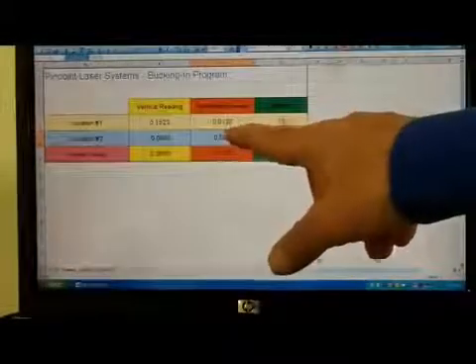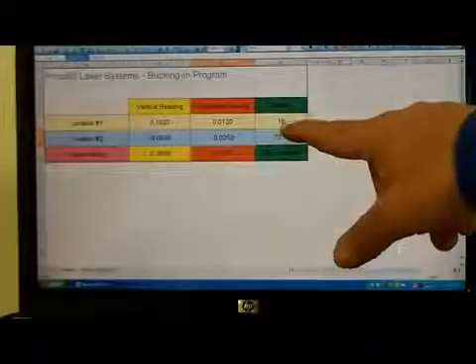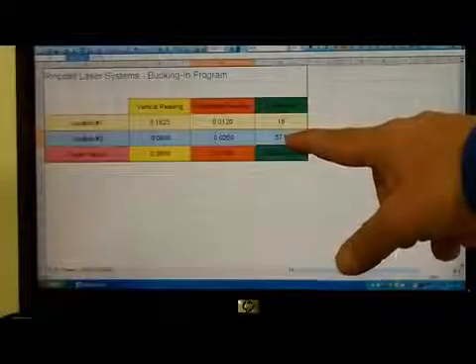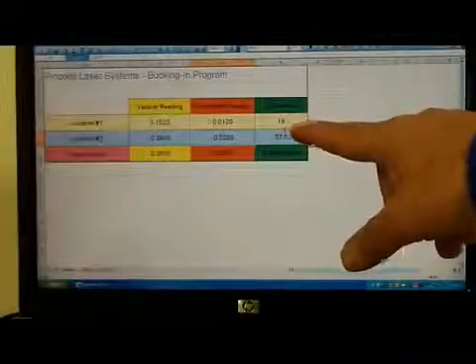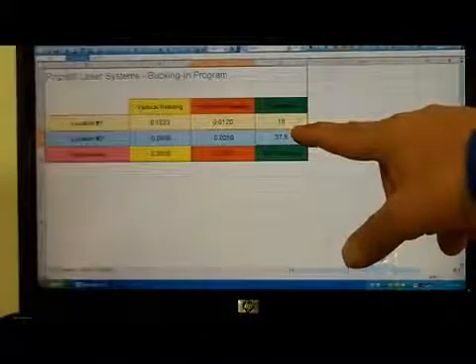So now I go ahead and enter my readings found at location one into the vertical reading and the horizontal reading. With this I also include the distance from the face of the laser to the face of the receiver in inches, which I've listed and documented here at 16 inches.